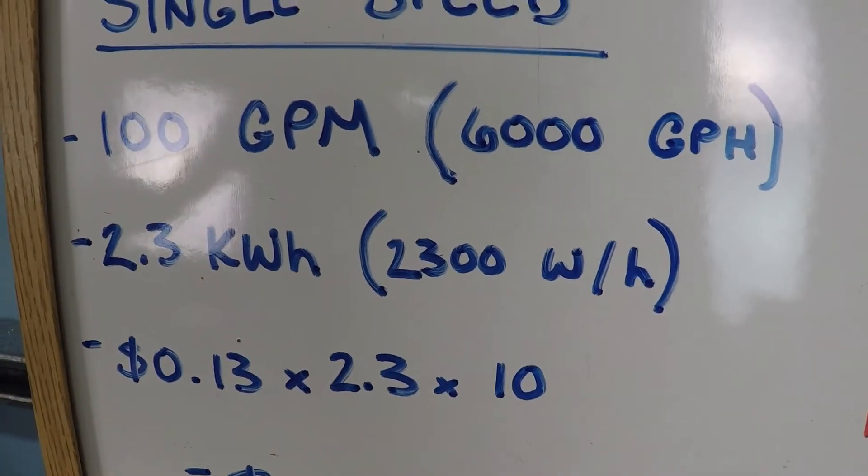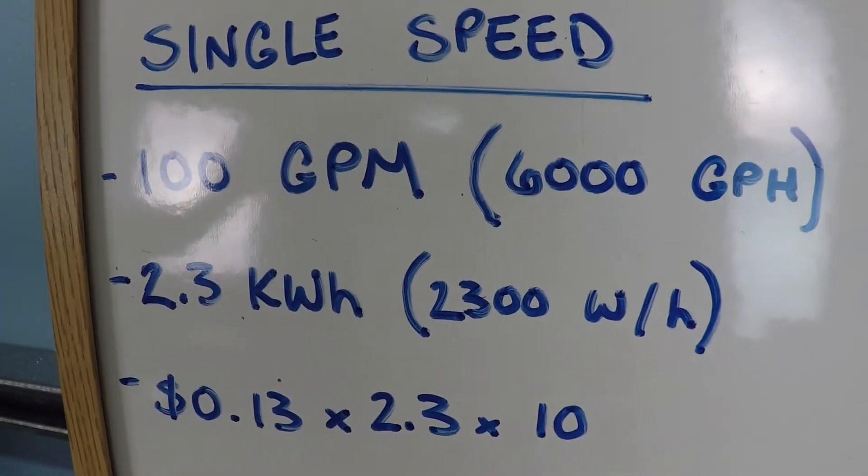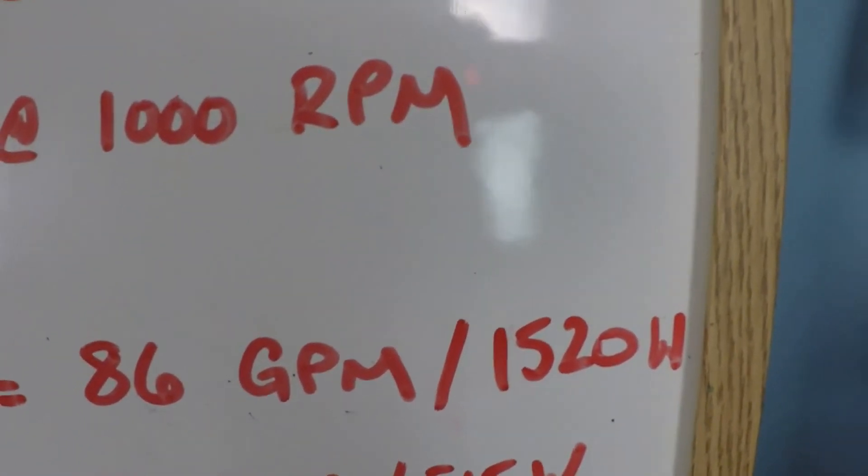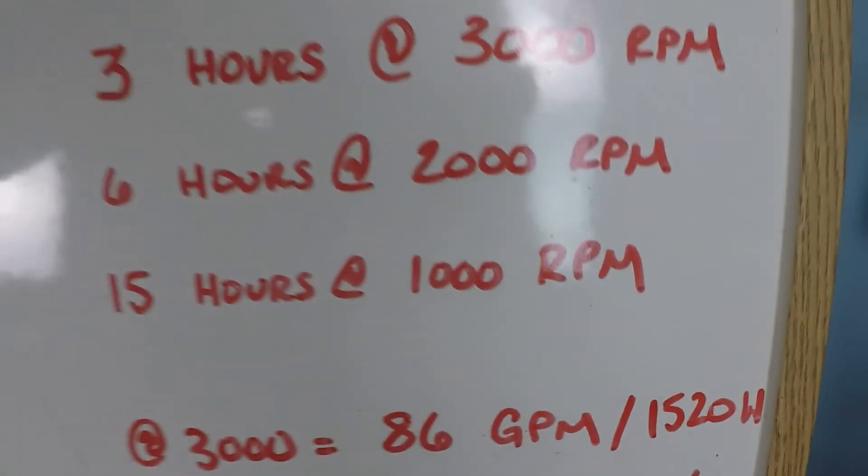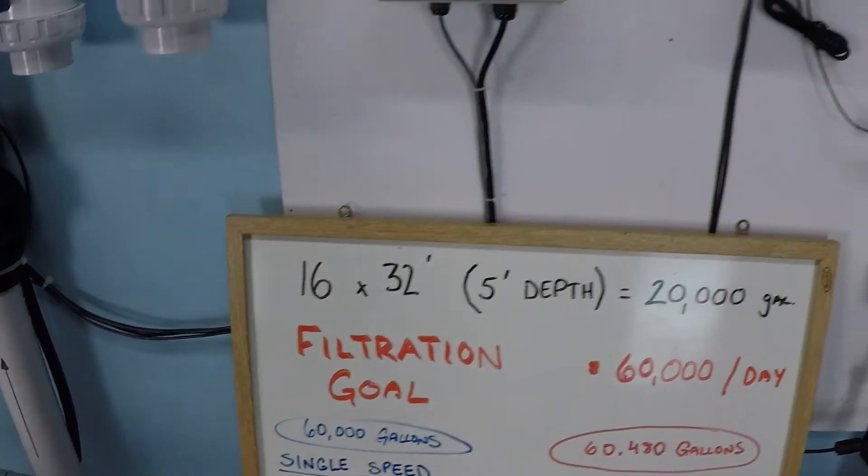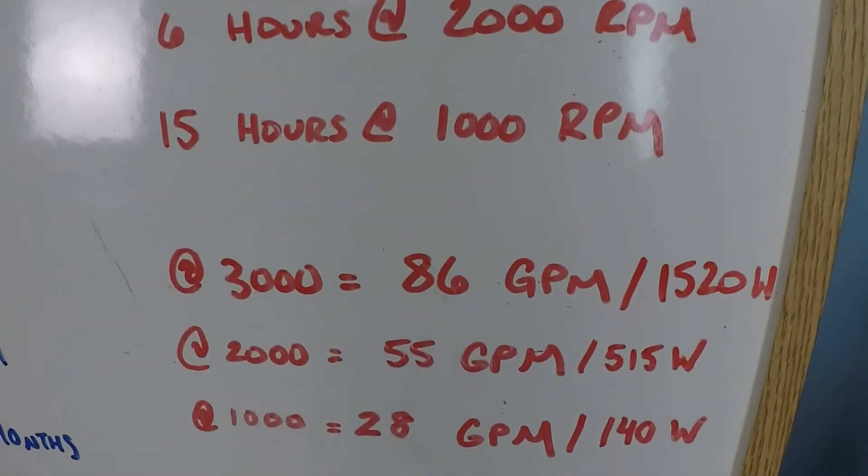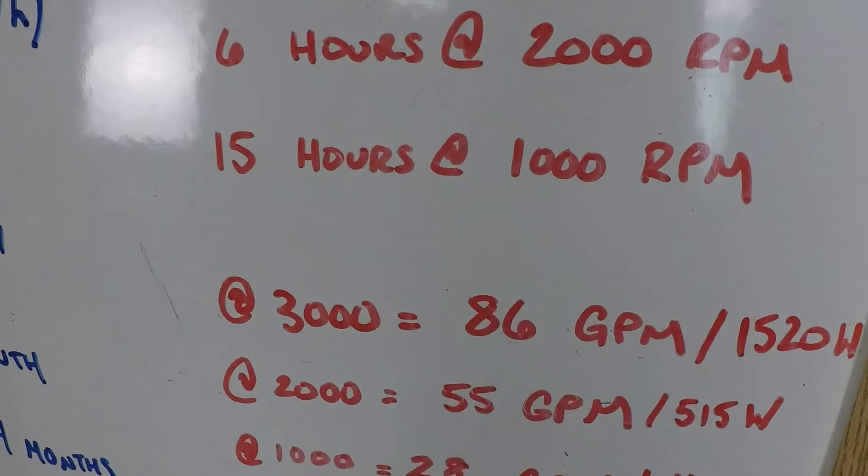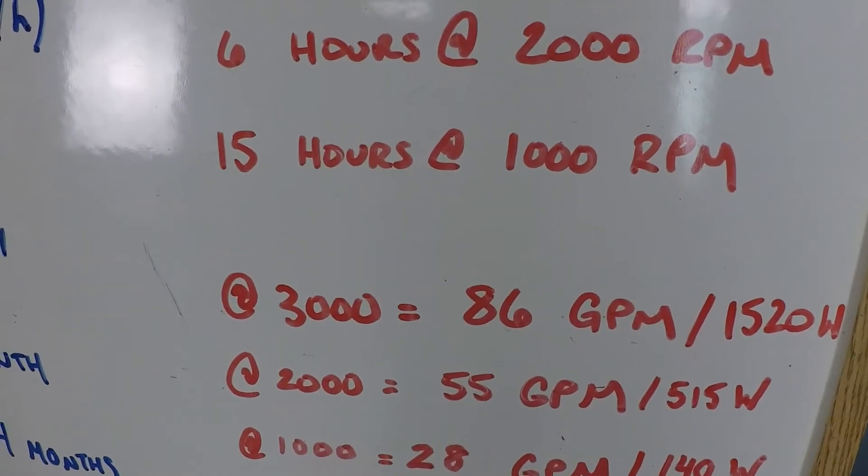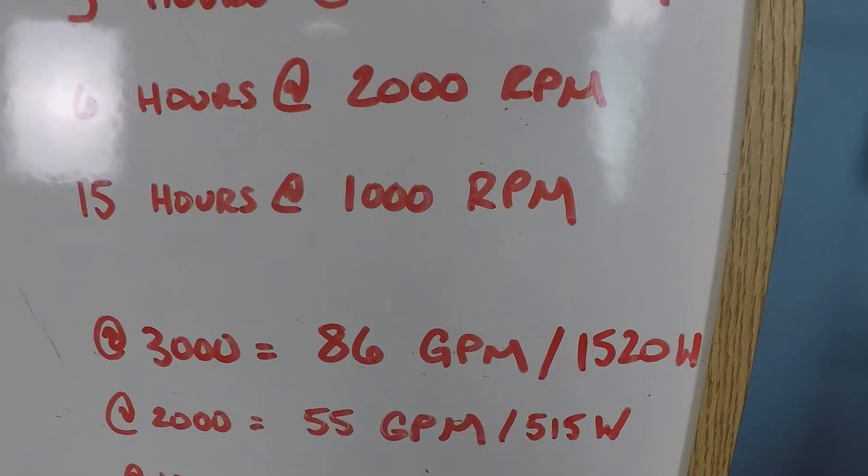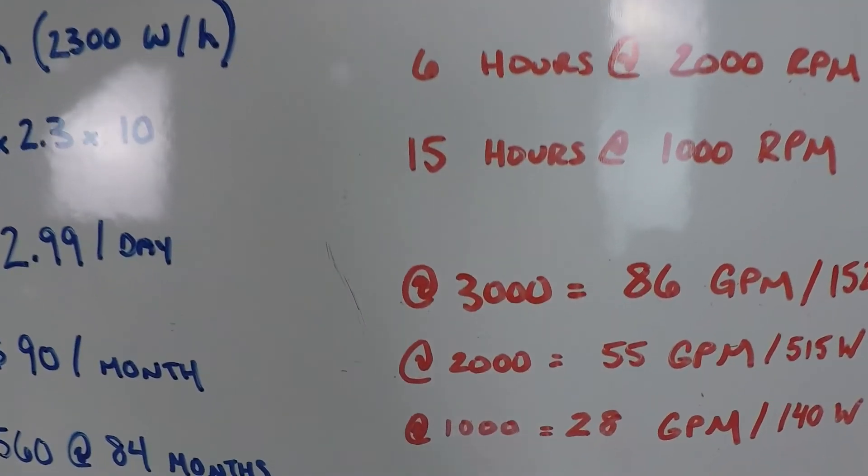So on this side, we had 2,300 watts per hour for 3,450 RPM. On this side, 1,520 watts. Our numbers were 1,530 just now, but these calculations are based on 1,520. And what that means for your flow is that for three hours every day, you're going to be getting 86 gallons per minute, and you're going to be paying 1,520 watts per hour. Now let's take a look at the slower speeds here.